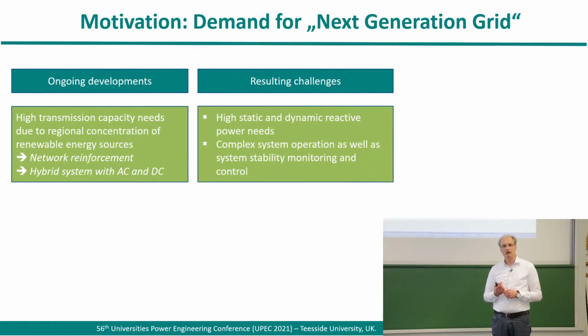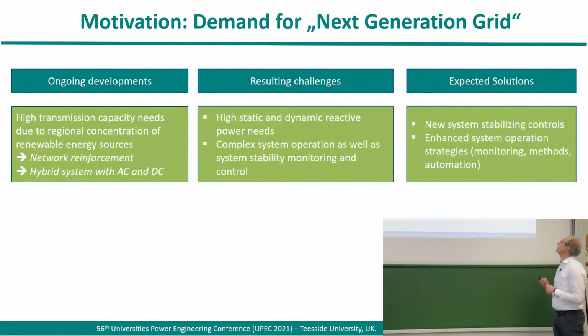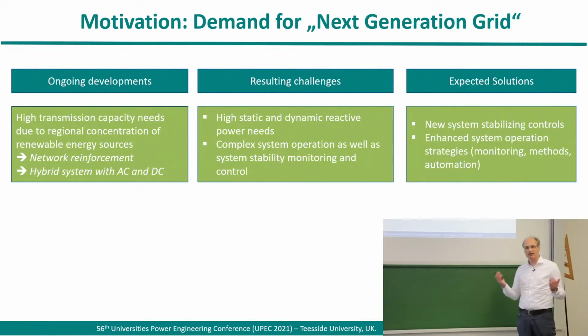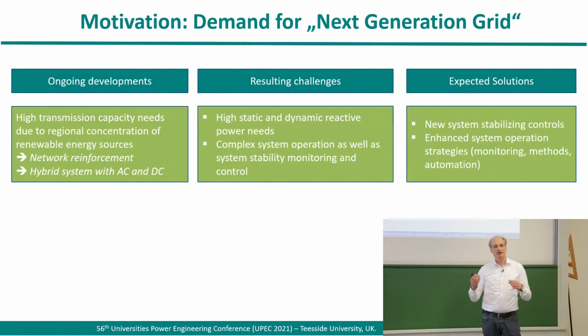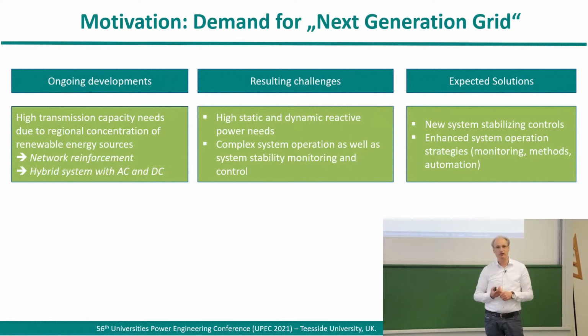Moreover, due to the highly different power flow situations in the network, we need both static and dynamic reactive power sources in the network. This can be solved by new system stabilizing components on the one hand, and on the other hand by enhanced system operation strategies, which really have to come from a system point of view, not just from a local control attitude.